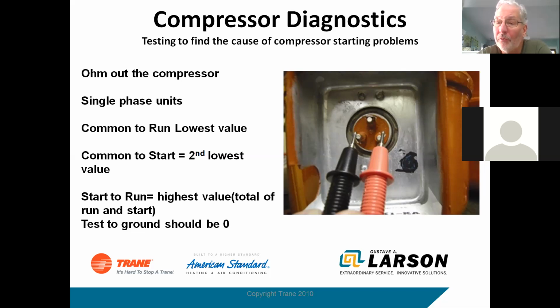common to run is going to be the lowest value. Okay, run is always the lowest value, and it's typically maybe around 1 ohm, 1.5 ohms, somewhere in that area. Okay, common to start is the second lowest. The start winding has more resistance because it's there to start the compressor, and then the total of the two should be our start to run.